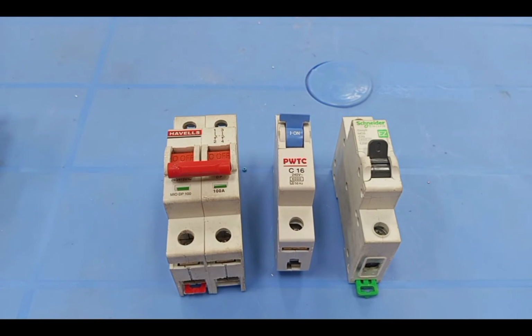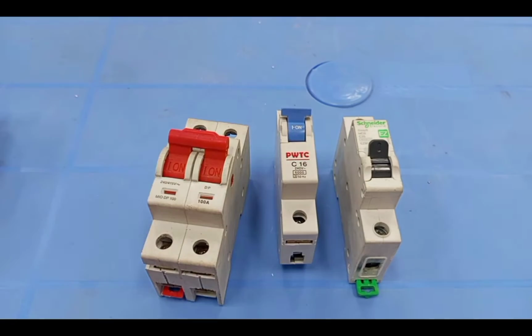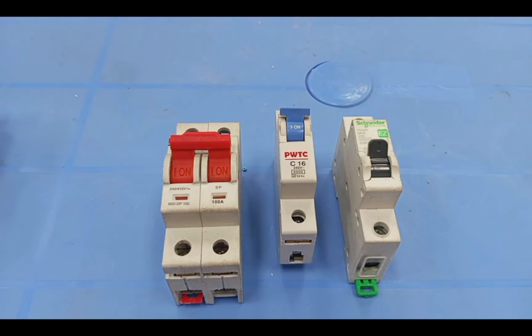All right. Now, what the miniature circuit breaker does is to protect the circuit, that is the cables and then the equipment in the wiring, from excessive current. And so to some extent, the miniature circuit breaker protects your property from electric fire. All right. Now, each miniature circuit breaker has a rating, and when wiring, you have to pay attention to the rating of the miniature circuit breaker. If you want to know more about how to select the correct size of miniature circuit breaker for your wiring, kindly refer to my previous video on how to select the correct size of breaker.